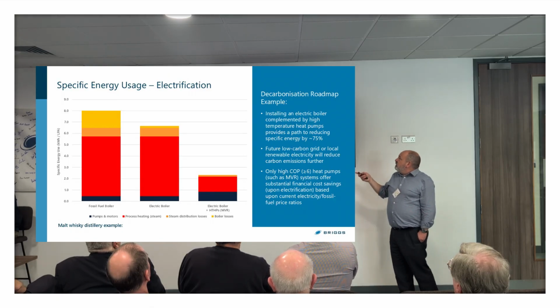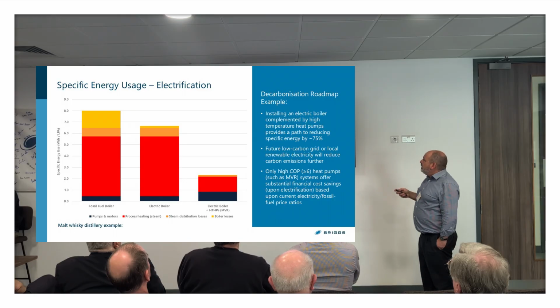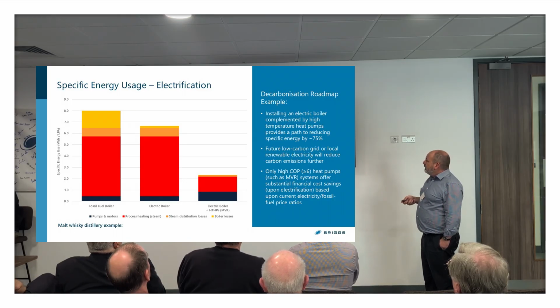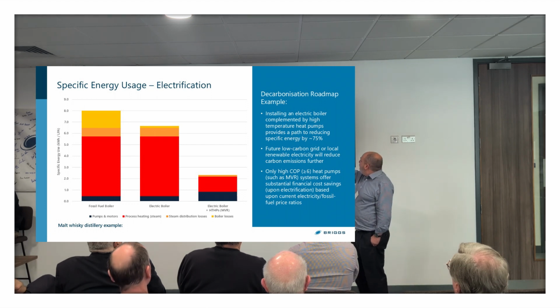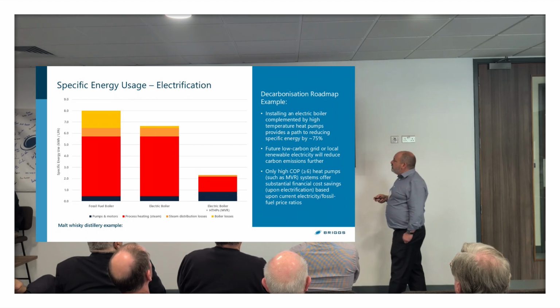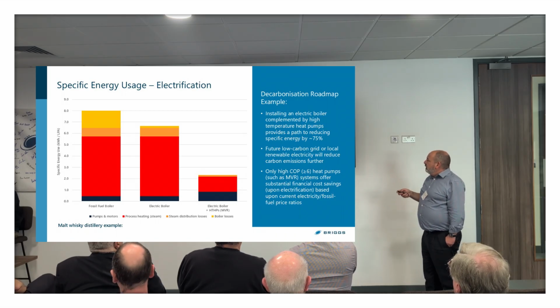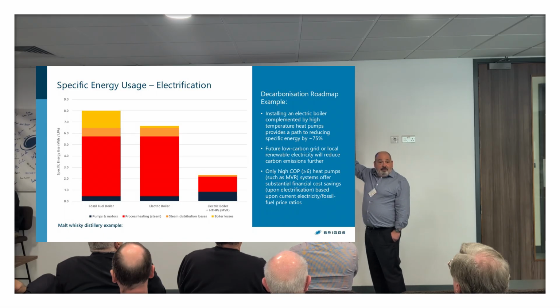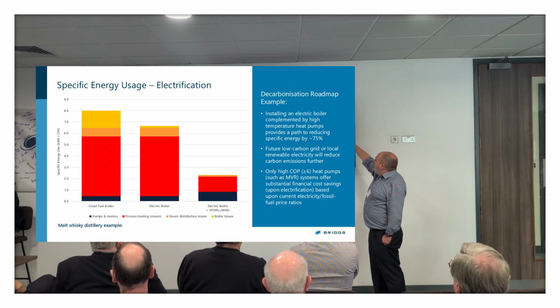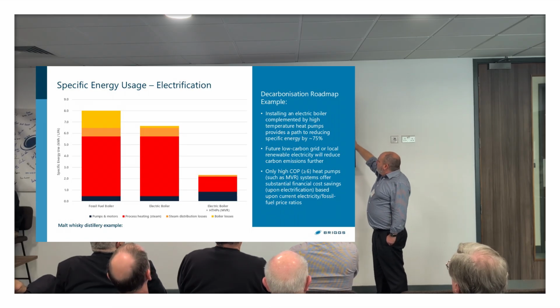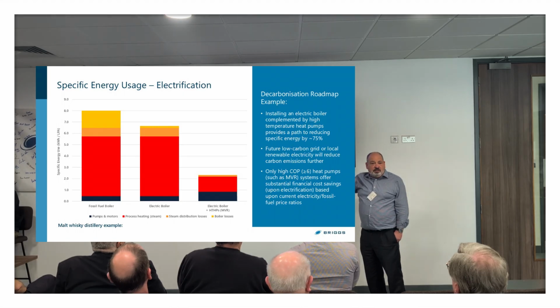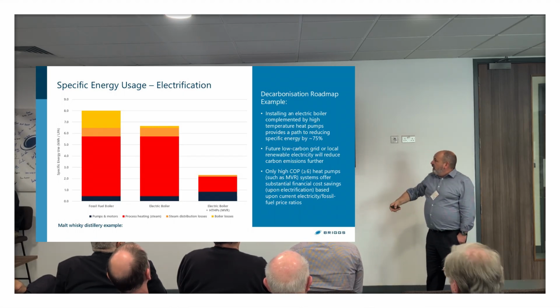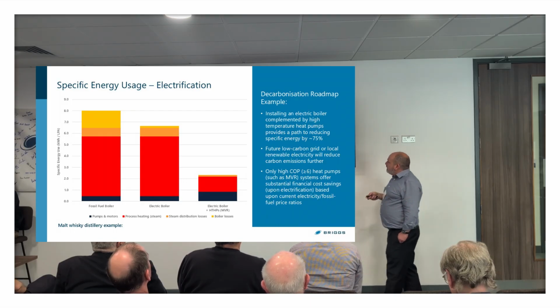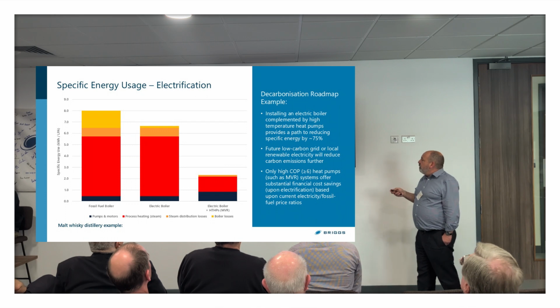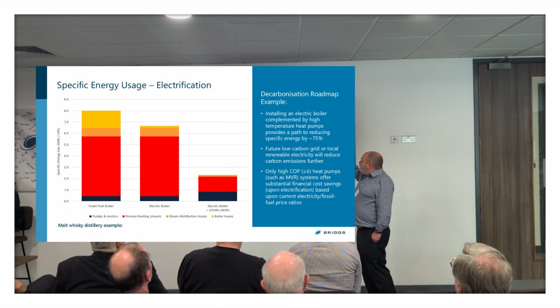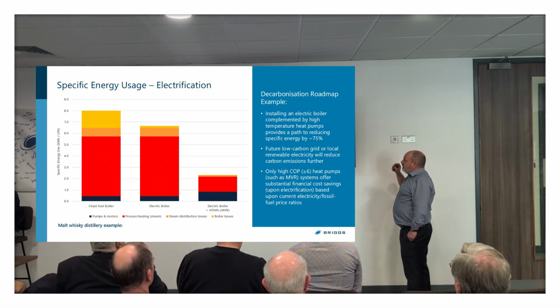So you can see that this gives us a decarbonisation roadmap, if you like. Install an electric boiler with the efficiency gains you have from that. That may or may not put you on parity on your CO2 emissions, but as the electricity specific emissions reduce, that will increasingly give you decarbonisation benefits.